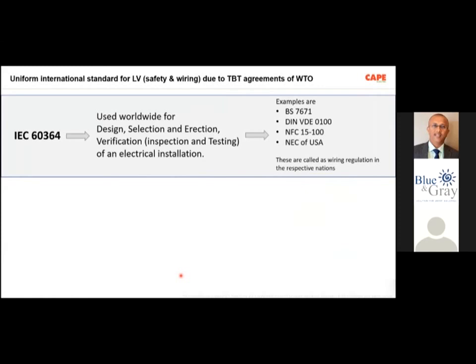Number two, how does this code of practice come? What is the basis? Who is making these requirements? So basically, worldwide, every country, be it America or European nations or the developed nations, everywhere uniform international standards for electrical safety are used. The same standard or the same systems are used everywhere, which is based on the TBT agreements of the World Trade Organization. The standard is called IEC 60364. This is the only standard which has to be referred to and used worldwide for design, selection, erection and verification of a low voltage electrical installation up to 1000 volt AC and 1500 volt DC.